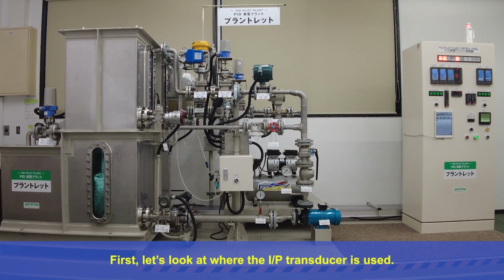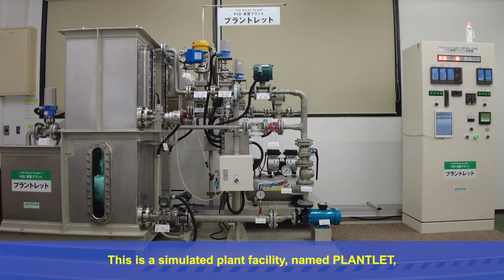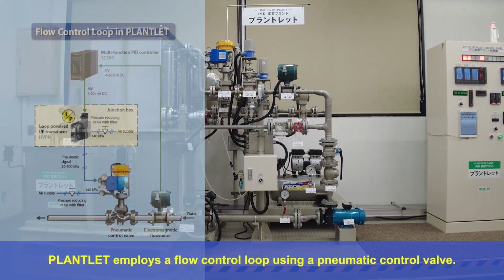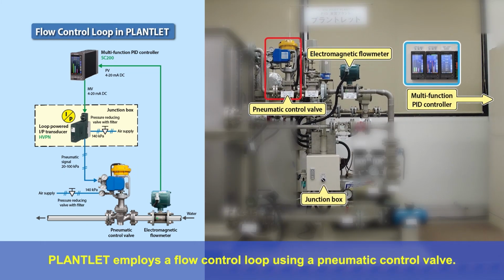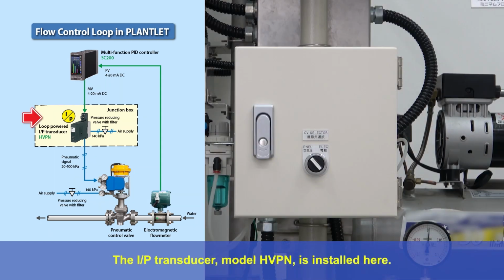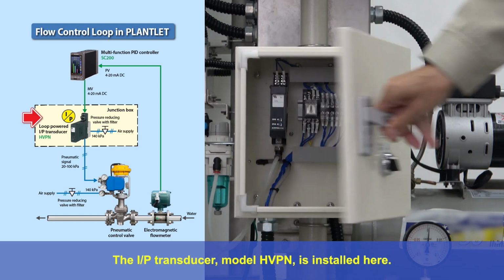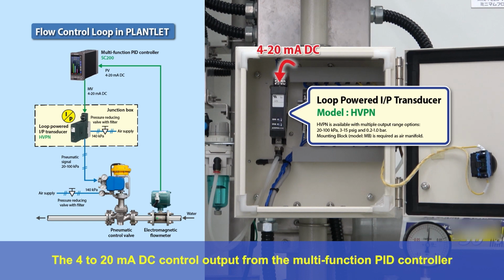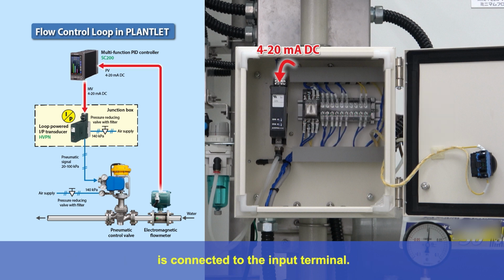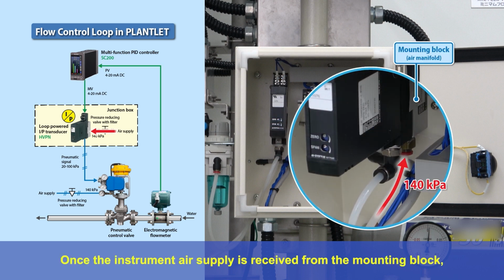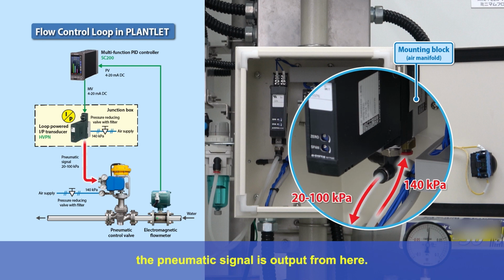First, let's look at where the I-to-P transducer is used. This is a simulated plant facility named Plantlet, installed at the headquarters of M-System. Plantlet employs a flow control loop using a pneumatic control valve. The I-to-P transducer, model HVPN, is installed here. The 4 to 20 milliampere DC control output from the multifunction PID controller, using the flow signal from the electromagnetic flow meter as an input, is connected to the input terminal. Once the instrument air supply is received from the mounting block, the pneumatic signal is output from here.